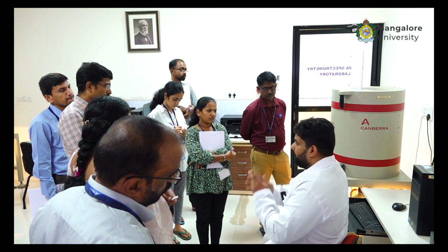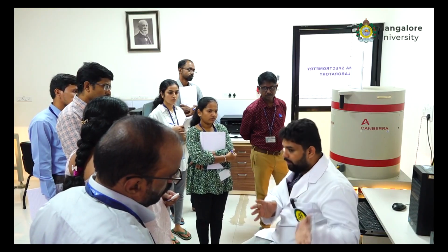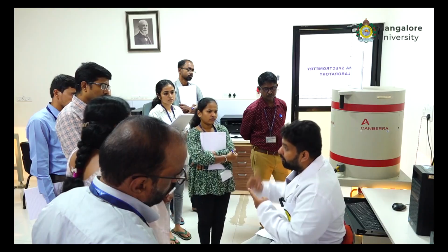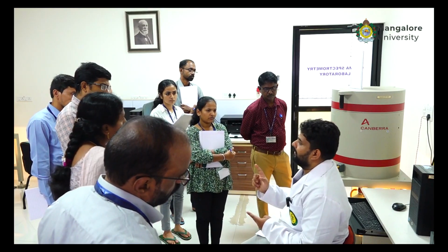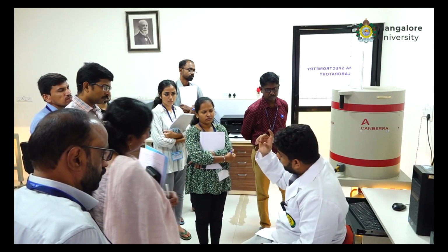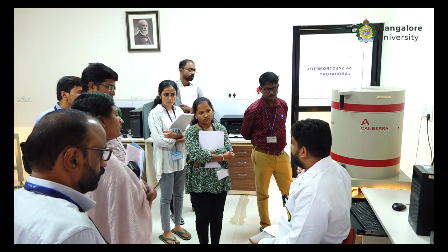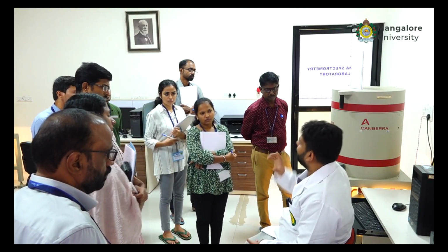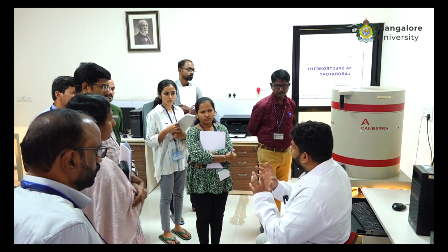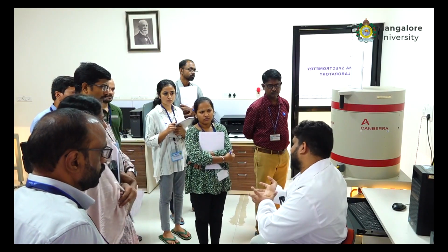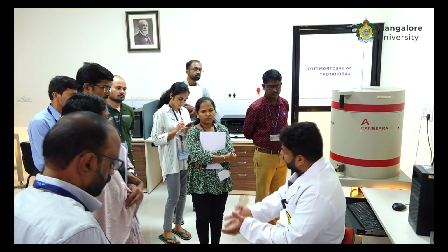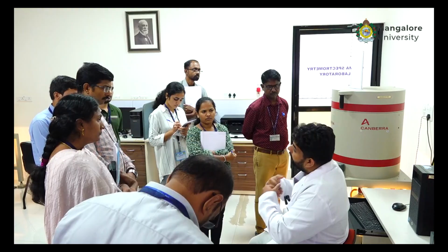That is why, while doing HPGe analysis or sodium iodide gamma spectrometry analysis, your sample geometry and your standard geometry should be the same and should have the same density. For example, if you use a water standard or a sand standard, and then use soil for your analysis, your results will vary largely. The density and material composition should be the same. Sand has its own standards, soil has its own standards, water has its own standards.